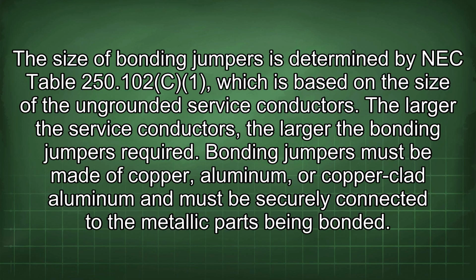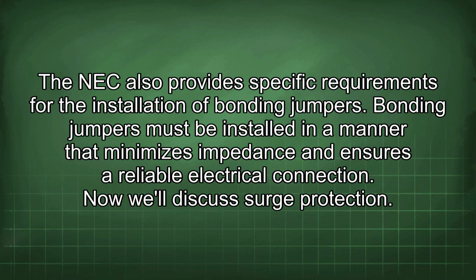The size of bonding jumpers is determined by NEC Table 250.102(C)(1), which is based on the size of the ungrounded service conductors. The larger the service conductors, the larger the bonding jumpers required. Bonding jumpers must be made of copper, aluminum, or copper-clad aluminum and must be securely connected to the metallic parts being bonded. The NEC also provides specific requirements for the installation of bonding jumpers. Bonding jumpers must be installed in a manner that minimizes impedance and ensures a reliable electrical connection.